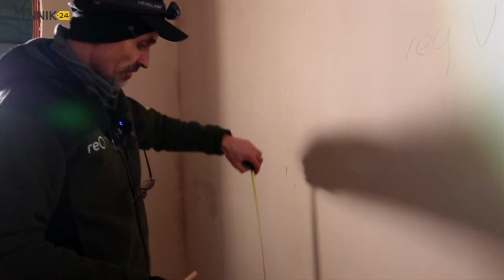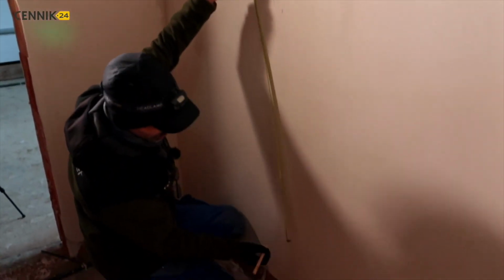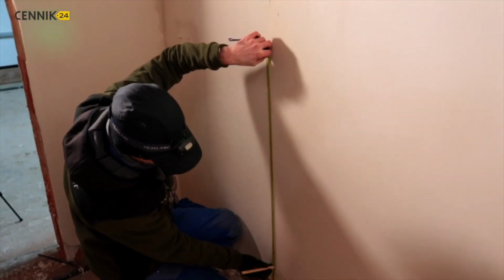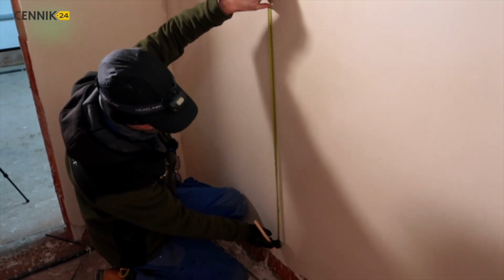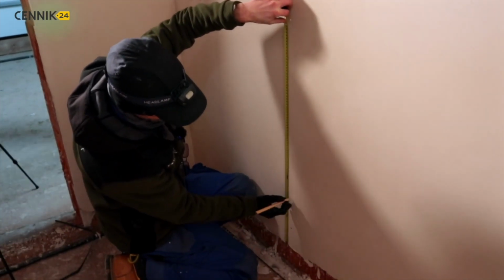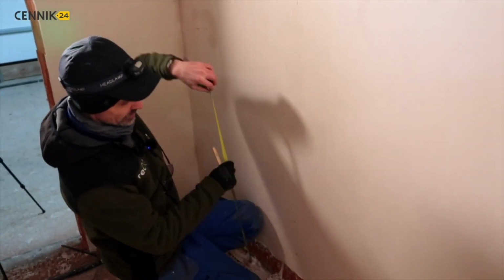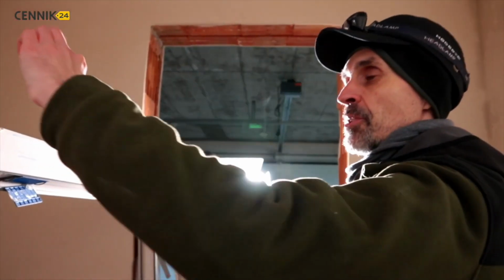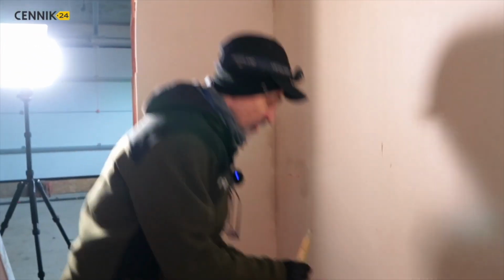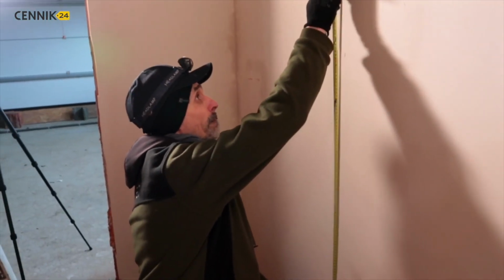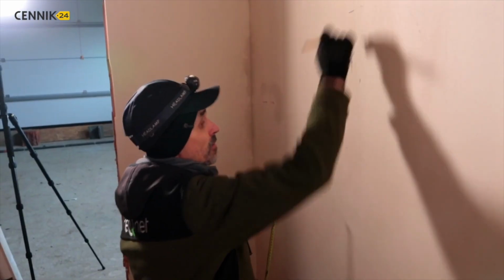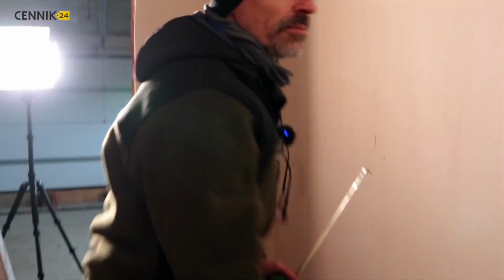The next parameter we need to maintain is the minimum height from the floor, from the surface, at least 100 millimeters, which is 10 centimeters. But for convenience and ease of use later on, it's better to leave about 25 centimeters. The ventilation unit has a height of 981 millimeters. So for practical purposes, let's round that up and assume a full 1000 millimeters for now. This means that in these designated spots, the ventilation unit will be situated and located.